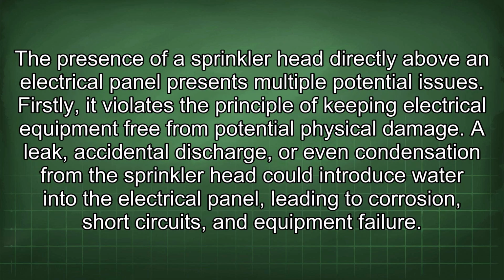The presence of a sprinkler head directly above an electrical panel presents multiple potential issues. Firstly, it violates the principle of keeping electrical equipment free from potential physical damage. A leak, accidental discharge, or even condensation from the sprinkler head could introduce water into the electrical panel, leading to corrosion, short circuits, and equipment failure.